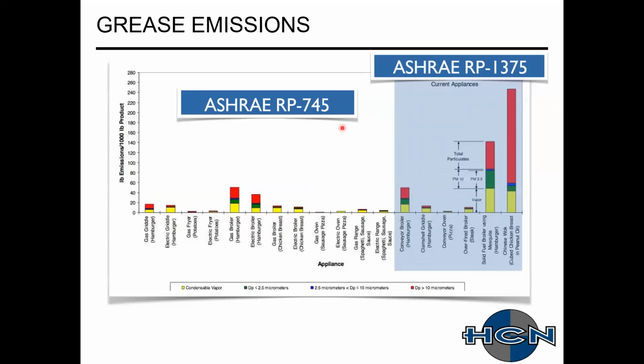So as I stated, ASHRAE did a couple of different research projects on this. 745 was back in the 90s. 1375 was back in 2008. And the big thing there was the efficiencies of these pieces of equipment have gotten drastically better. So they're putting off a lot more effluent that we need to capture. And this is basically going over what types of effluent you're getting off of there. Typically, with most mechanical filters, you're looking at the green area and above. Vapor, you typically can't capture with a mechanical filter.